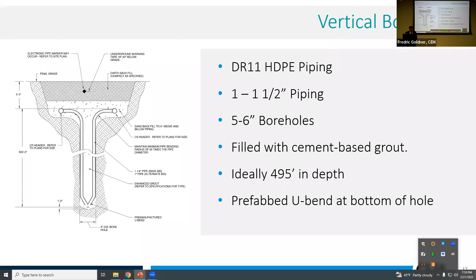Okay, ground heat exchanger sizing. This is the bore field. Manny mentioned annual heating and cooling loads will affect the overall size of this bore field. The peak heating and cooling loads are very important as well. Bore spacing, grout conductivity, ground temperature, and the approach temperature.